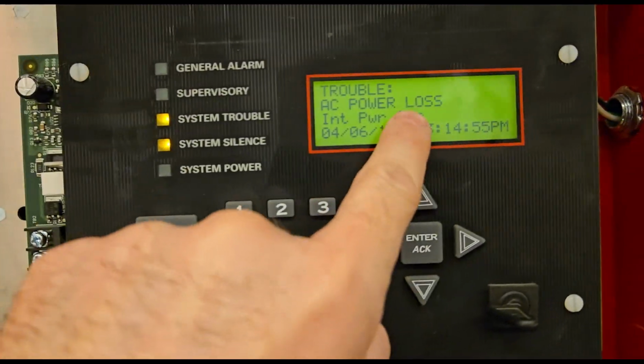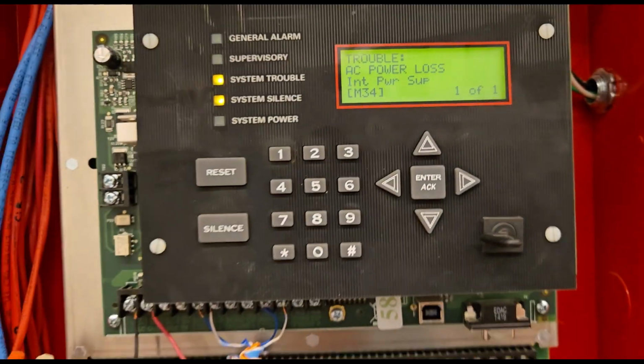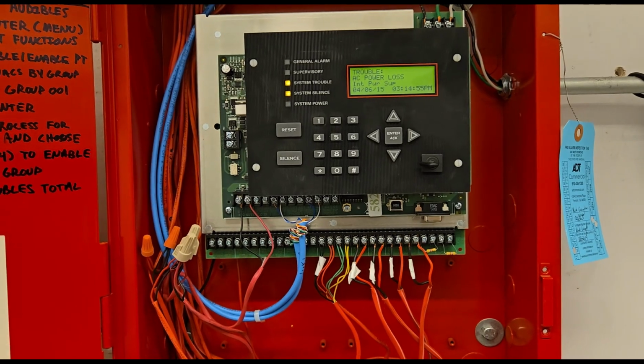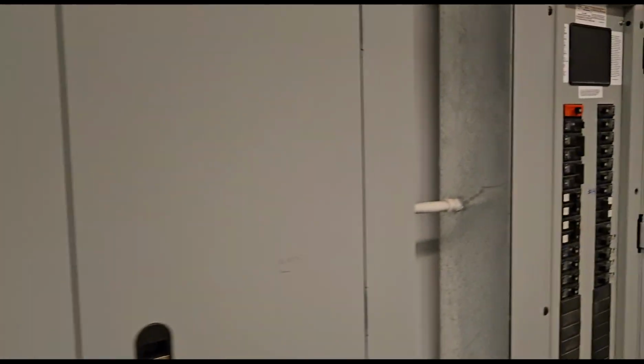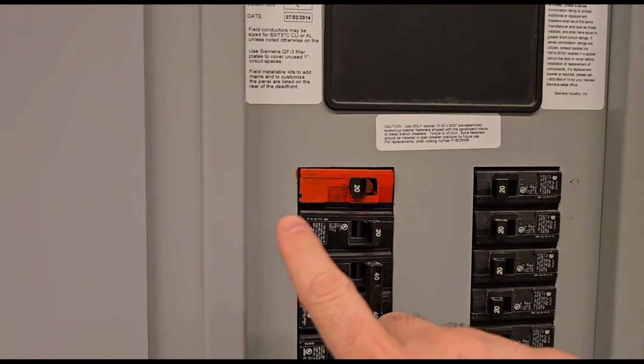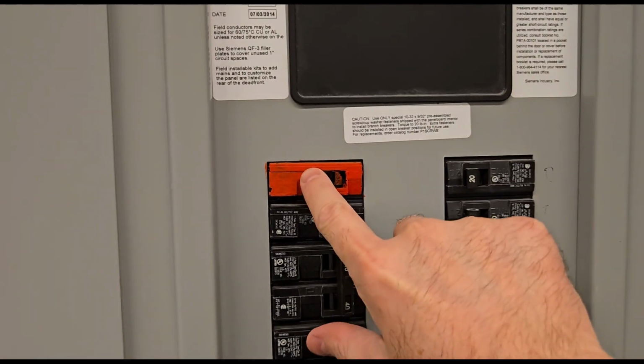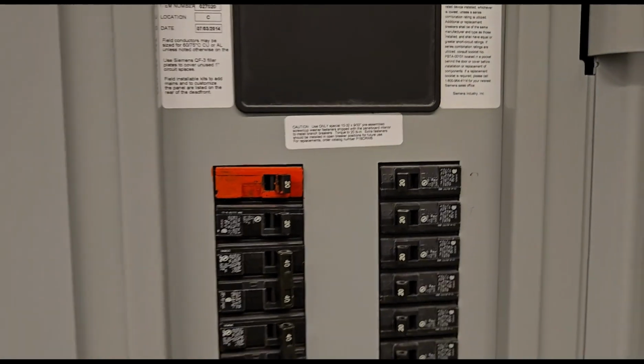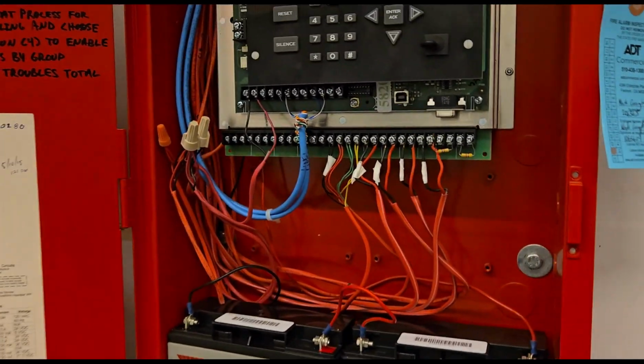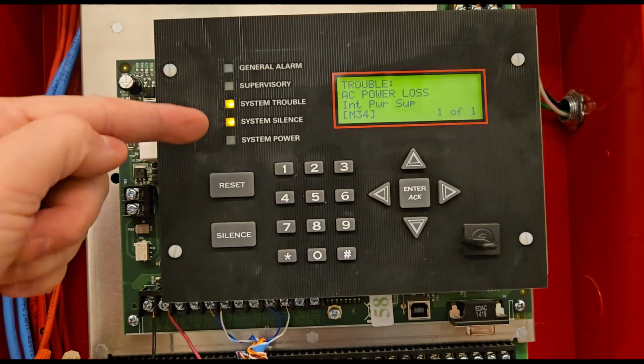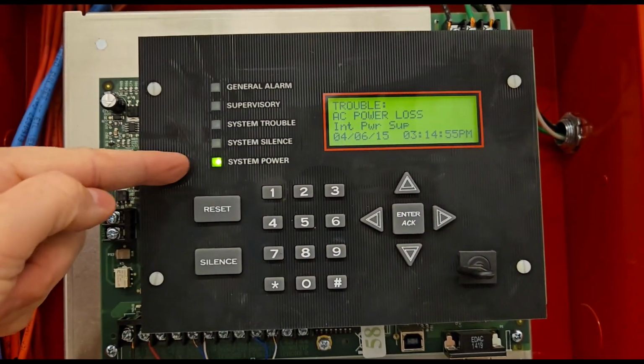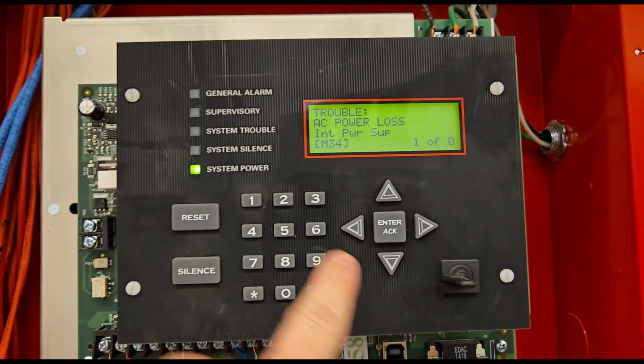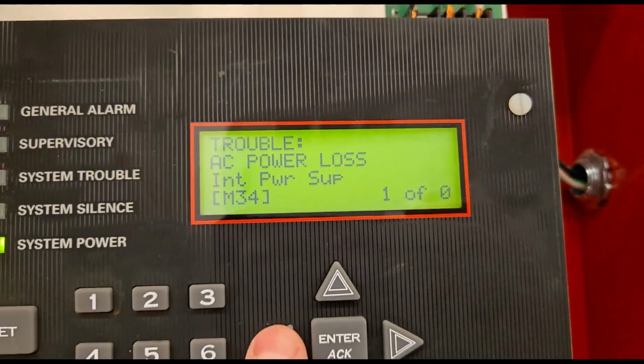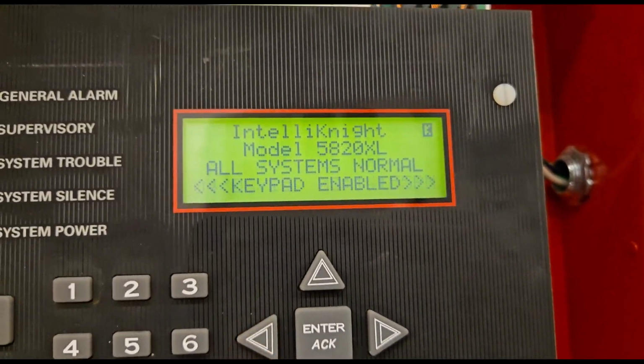So we still have this trouble. So now that we've completed our circuit breaker test, now we're going to flip the power back on. So come over to our panel, our circuit breaker panel, flip our circuit. Go ahead and close this because we don't need it. Go back over to our panel. We should see this light come on, and there it goes. Light's back on. Trouble lights have cleared. I'm going to hit the back button to clear out of this message, and we should be all clear.